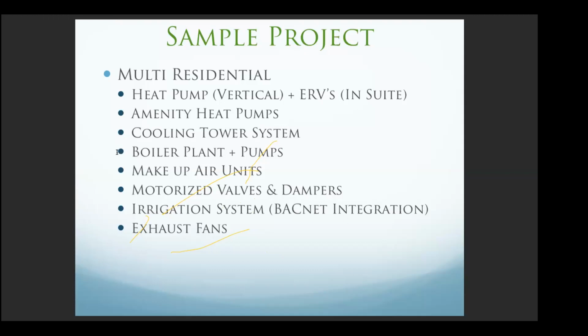Boiler plants, same thing. We just talked about the boiler plant in the previous example, depending on if it is coming with a BACnet card or not, we may integrate it in that fashion. And if it's not, then we may need to provide a controller and wire up all the points. Same thing with the pumps, depending on if the pump has a VFD or not, 2 points versus the 5 points we discussed in the previous example and in the question.